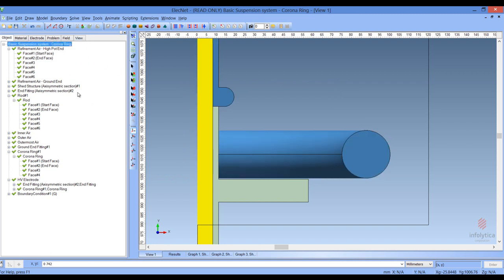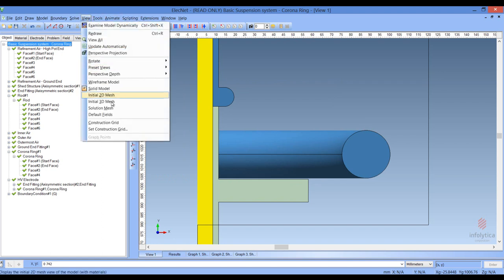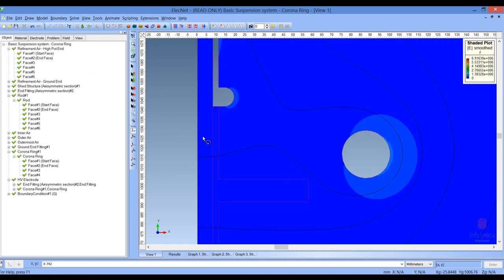Let's view what the solution looks like for this configuration. As you can see, the corona ring is actually reducing the electric stress around the end fitting, as indicated by the much lighter color here. As we did before, let's examine the electric field stress along the three contours defined in the EPRI document.